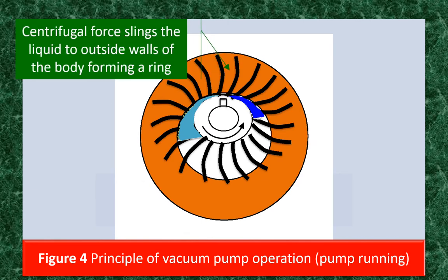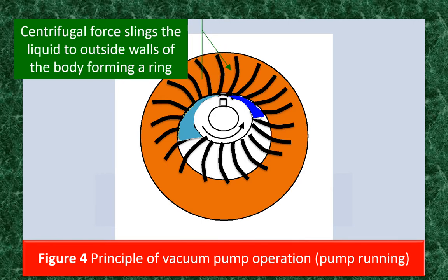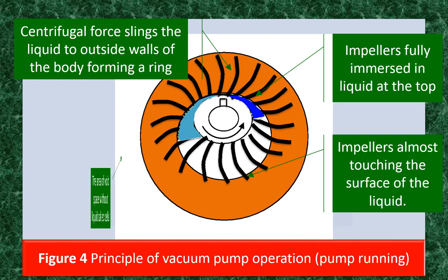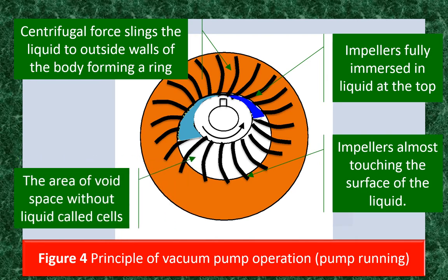When the pump starts, the impeller slings the liquid sealant by centrifugal force to the outside walls of the body, forming a ring of liquid at the outside walls. Because the impeller is offset from the body, some of the blades are fully immersed in liquid and some are almost out of the liquid. The area of void space without liquid is sealed off between the liquid — hence the term sealant — and between the impeller blades, called an impeller cell.